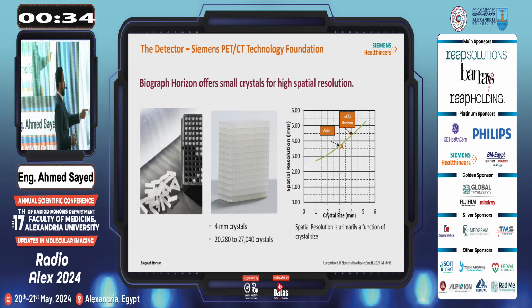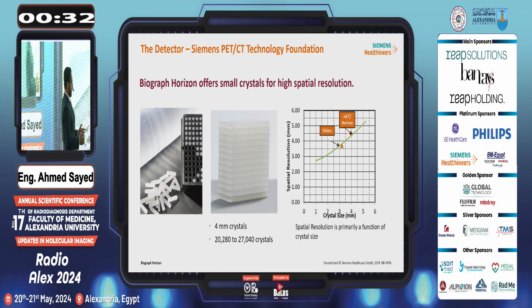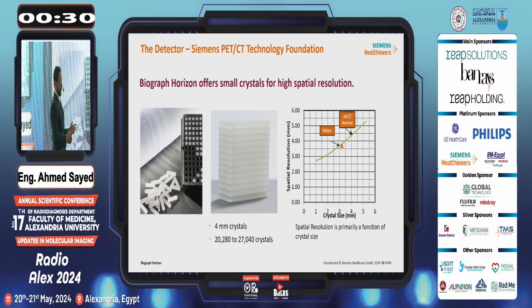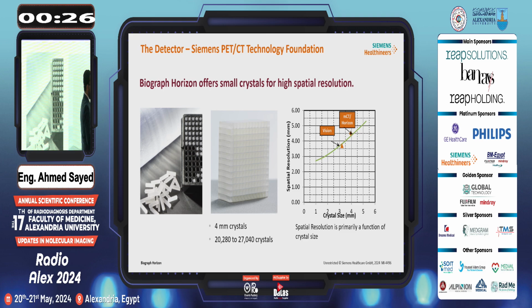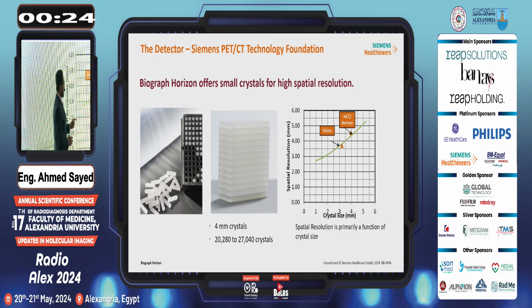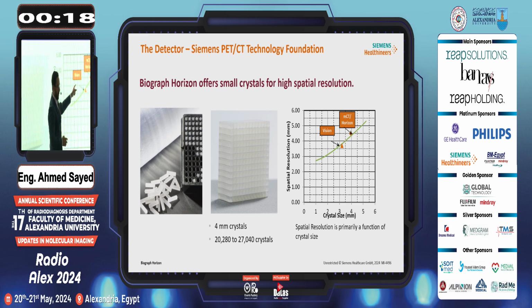These graphs show the impact of crystal element size on the spatial resolution. We have two crystal element sizes: one for Biograph MCT and Horizon is 4 millimeter, and Biograph Vision is 3.2 millimeter. The smaller crystal size gives us an improved spatial resolution.